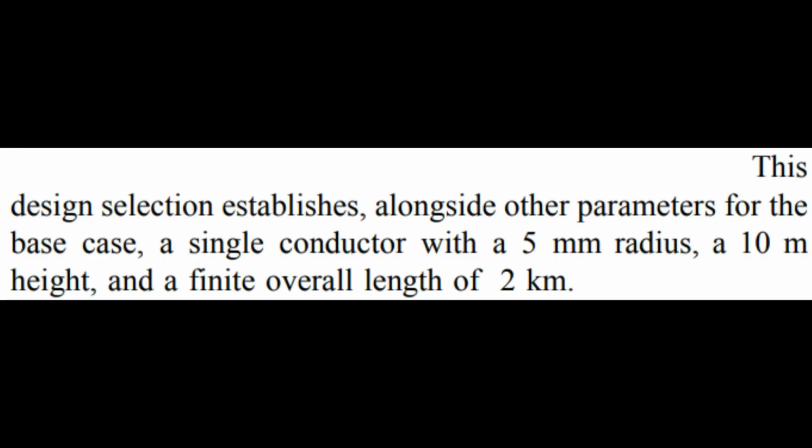The design of the base case is defined in accordance to the regulations for medium voltage network installations proposed in the ASTM B232 manufacturing standard. The chosen ACSR line is a Raven model, one AWG gauge, one Class A zinc-coated steel cord, and 6 1350 H19 aluminum wires concentrically wired. The design will also have poles placed every 100 meters and fixed value resistors with the same value of the characteristic impedance, 497.3 ohms, added to each end of the line to avoid reflections. The chosen test cases are three.